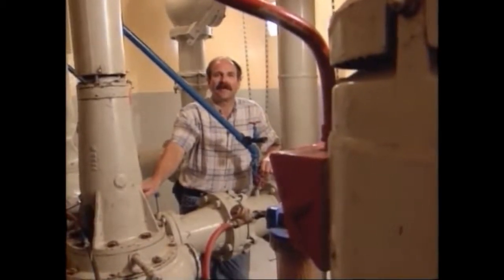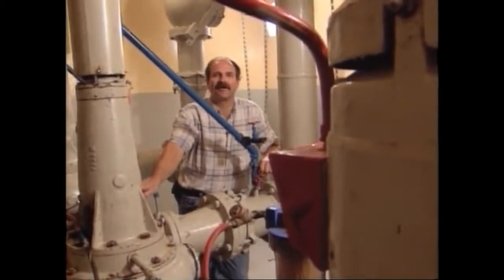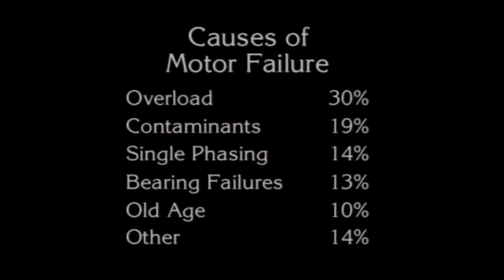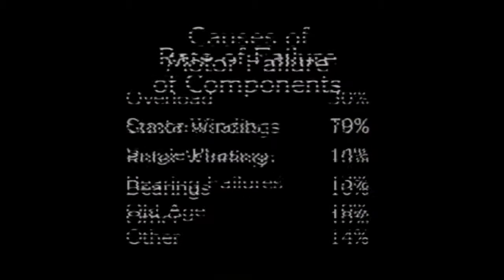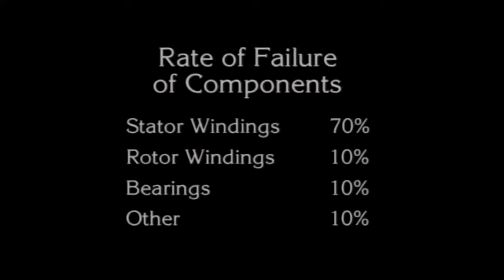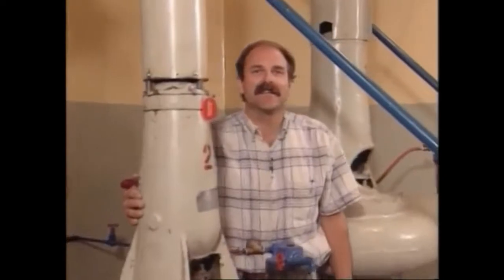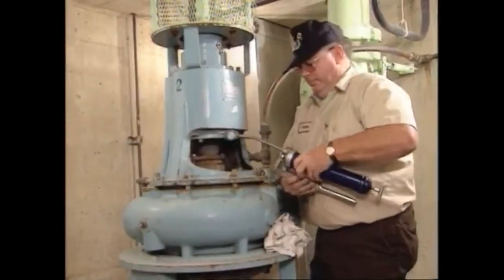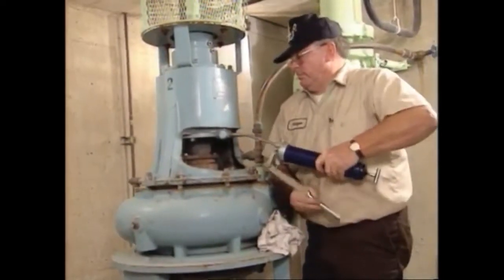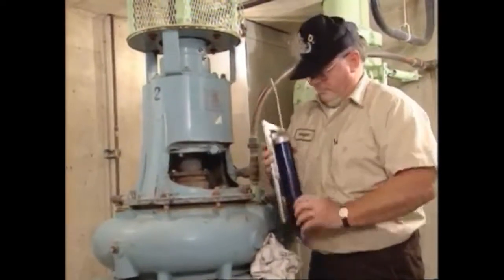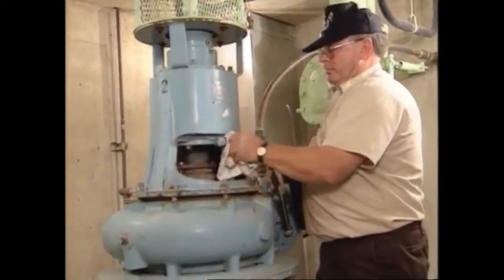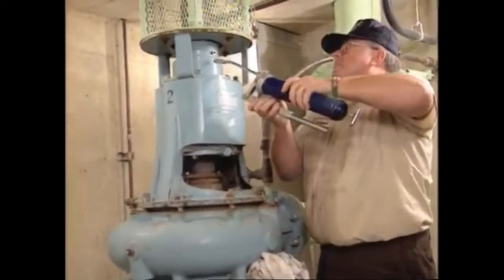The reasons for AC induction motor failures are overload, contaminants, single phasing, bearing failures, and old age. The most common components to fail in motors are stator windings, rotor windings, and bearings. Studies indicate that a large percentage of motor failures can be prevented. Overload, single phasing, and contaminants are responsible for 63% of motor failures. The good news is that all of these factors can be controlled by the operator.